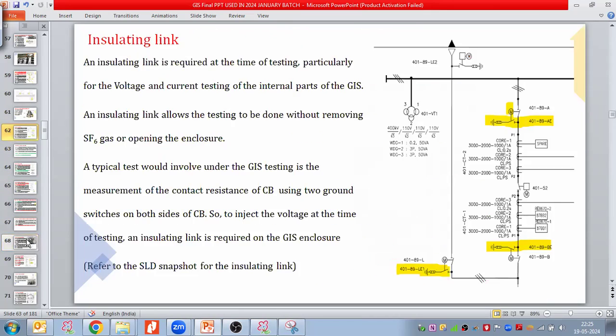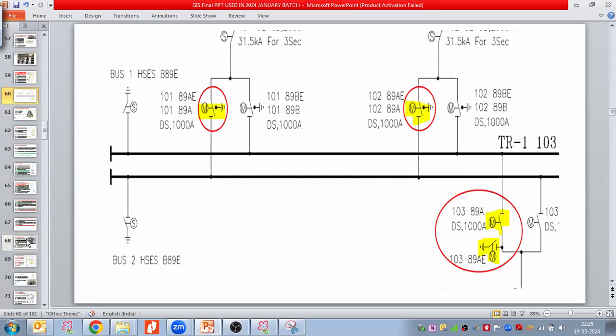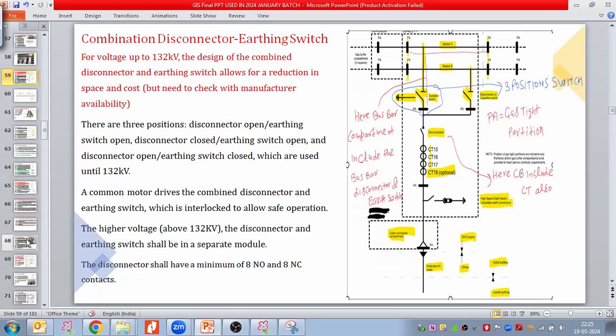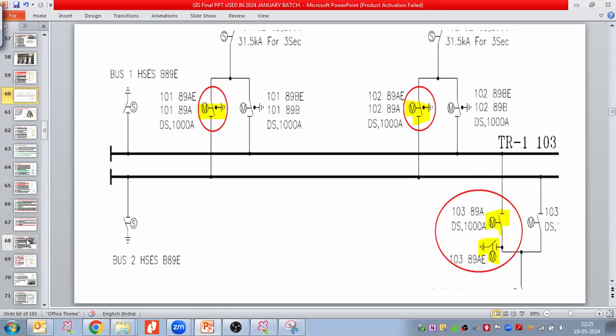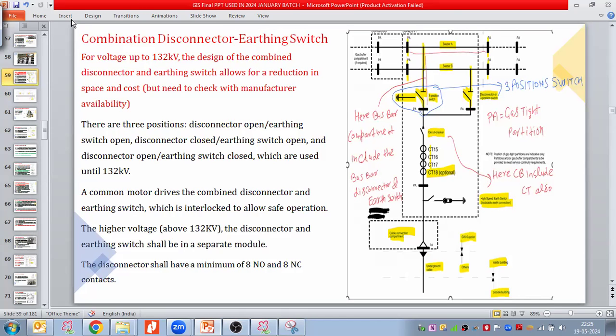Yes, sir, clear, sir. But sir, one operation I want to understand. Whenever the system is faulted, then the breaker will be off in sequence, and after that the high speed earth switch is connected, same as we have discussed in the AIS, the same switching sequence here. Means the high speed earthing switch has to operate automatically, no, sir? No, it will not. They operate on command, same as we discussed in the AIS.